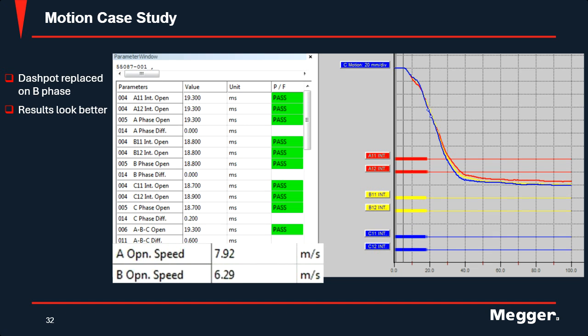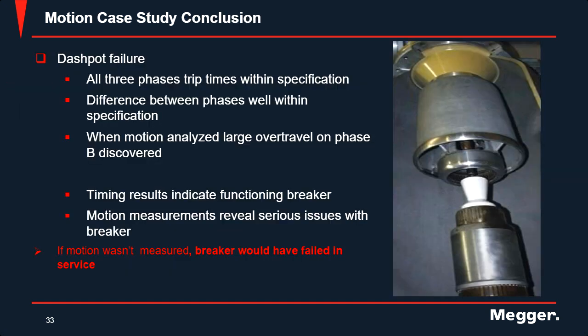So what's the point of this story? All three phases were timed and fell within spec. If they would not have done motion analysis on that breaker, B phase would have failed. It would have been a matter of time before that linkage broke, either in the next operation or the next couple. So the moral of the story is, don't neglect doing motion on your breakers.